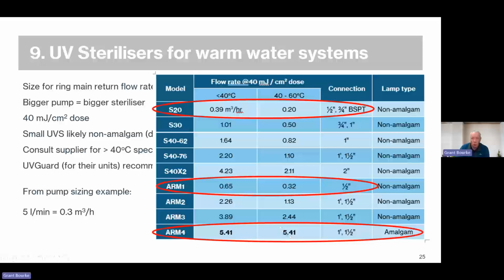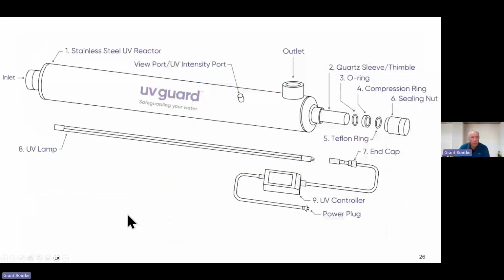On the small buildings, because we want small units and they're less expensive, we usually go with a non-amalgam lamp, but we need to make an allowance by consulting the manufacturer for the fact that we're not going to get the full dose at that higher temperature. So if we have a look at a typical UV sterilizer, it's a long stainless steel tube looking thing hanging on the wall. As I said before, we need to leave enough room out the end to get the lamp out.